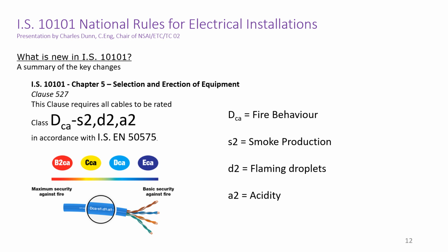Ireland has now in fact adopted a mid-range standard, as EN 50575 has cable ratings from ACA to FCA. Ireland will look for class DCA as the new minimum standard for all buildings. The new mandatory cable standard does not prevent specifying a higher class, say class CCA, for particular installations, but the minimum mandatory for all buildings shall be class DCA.